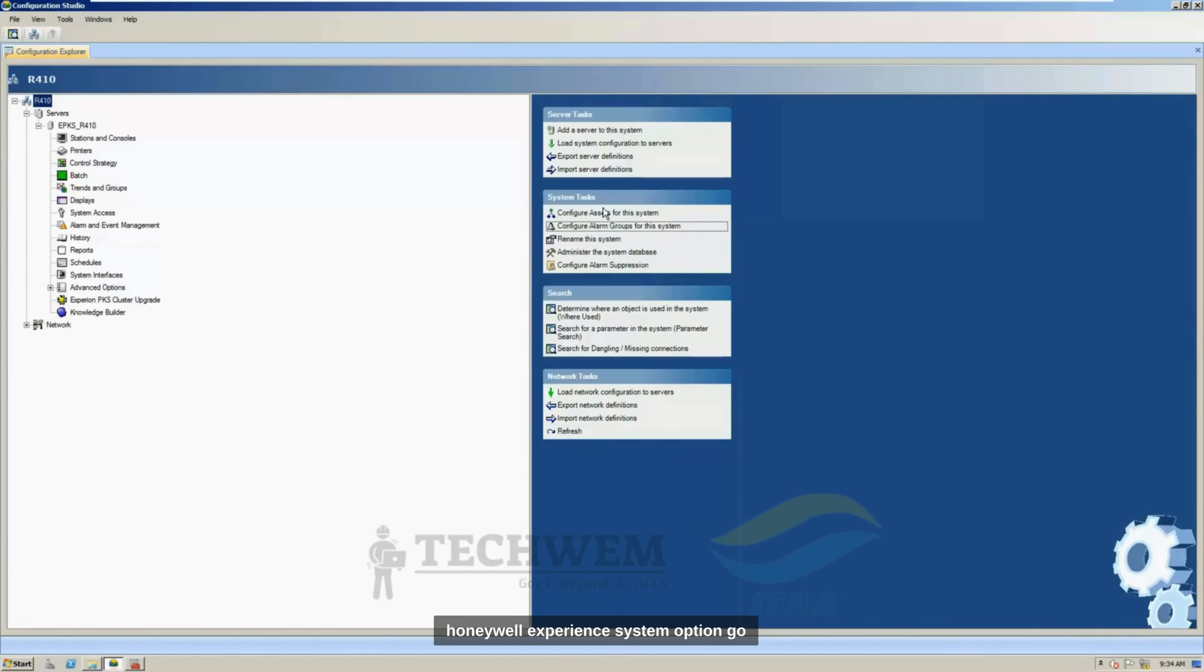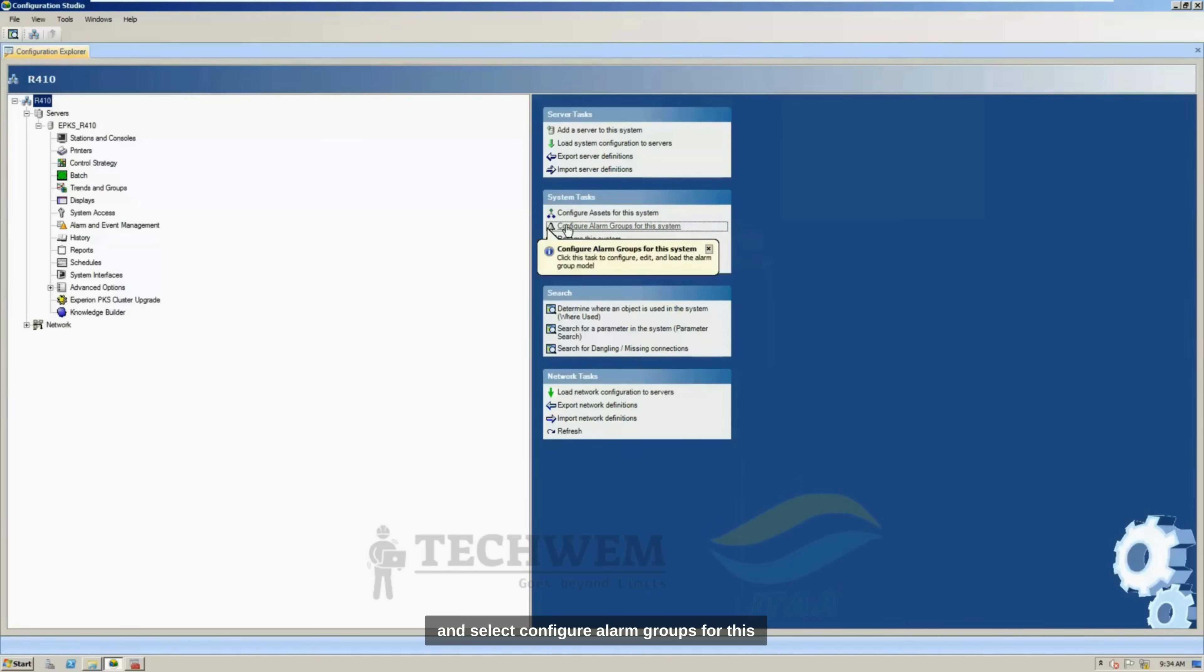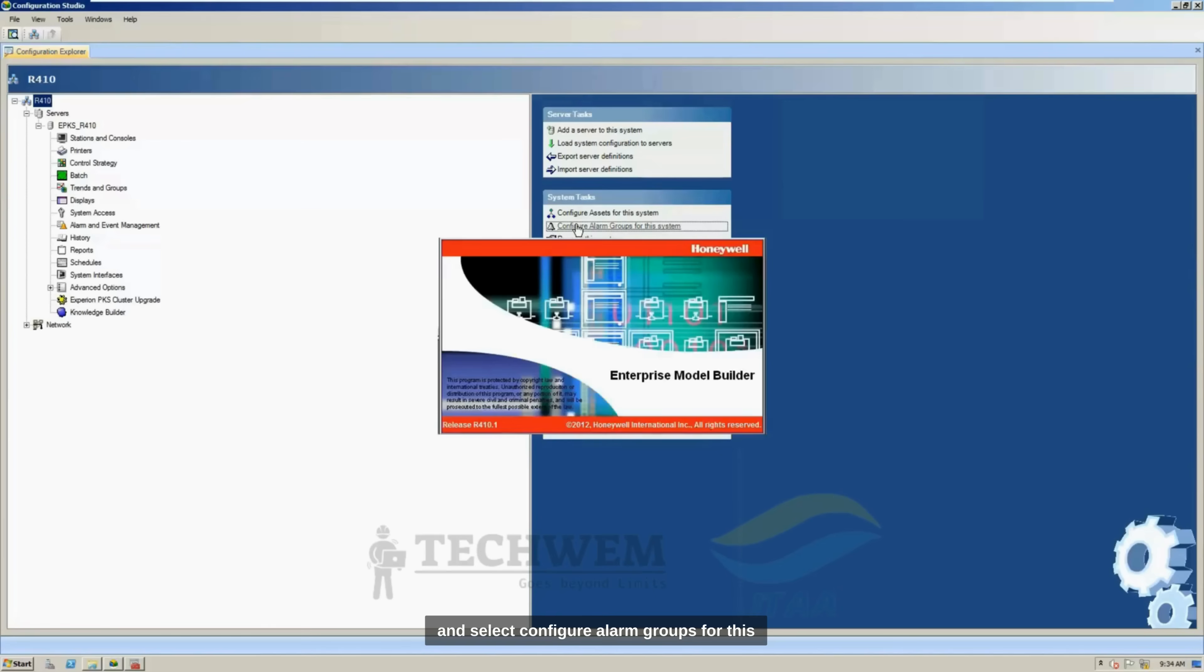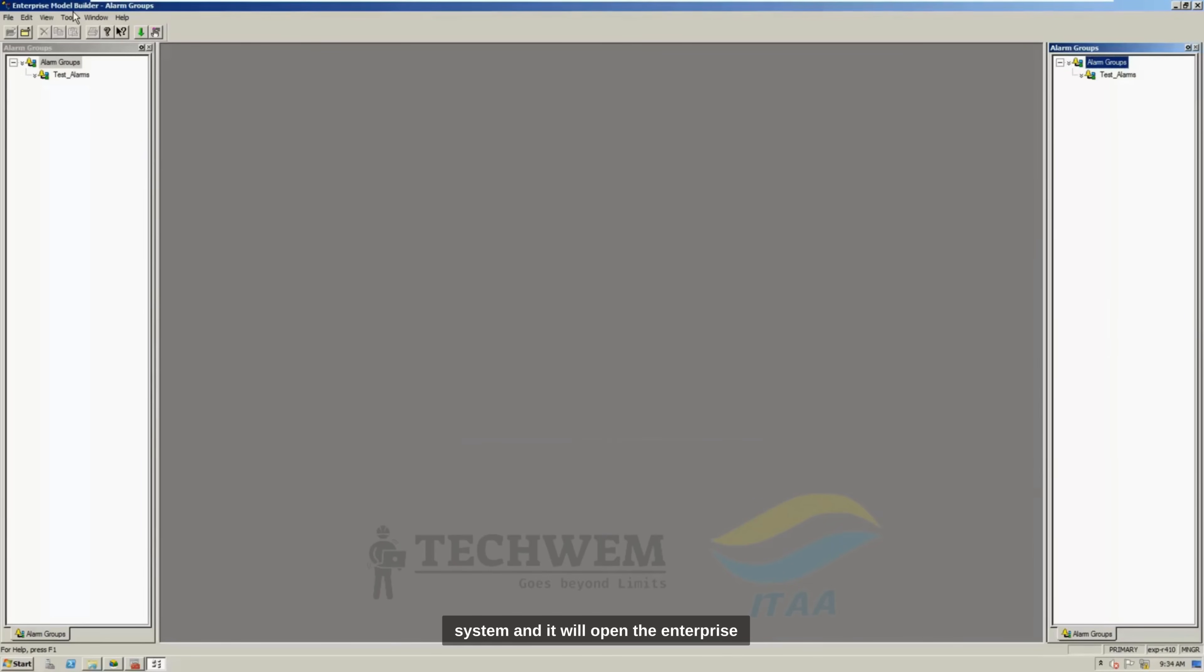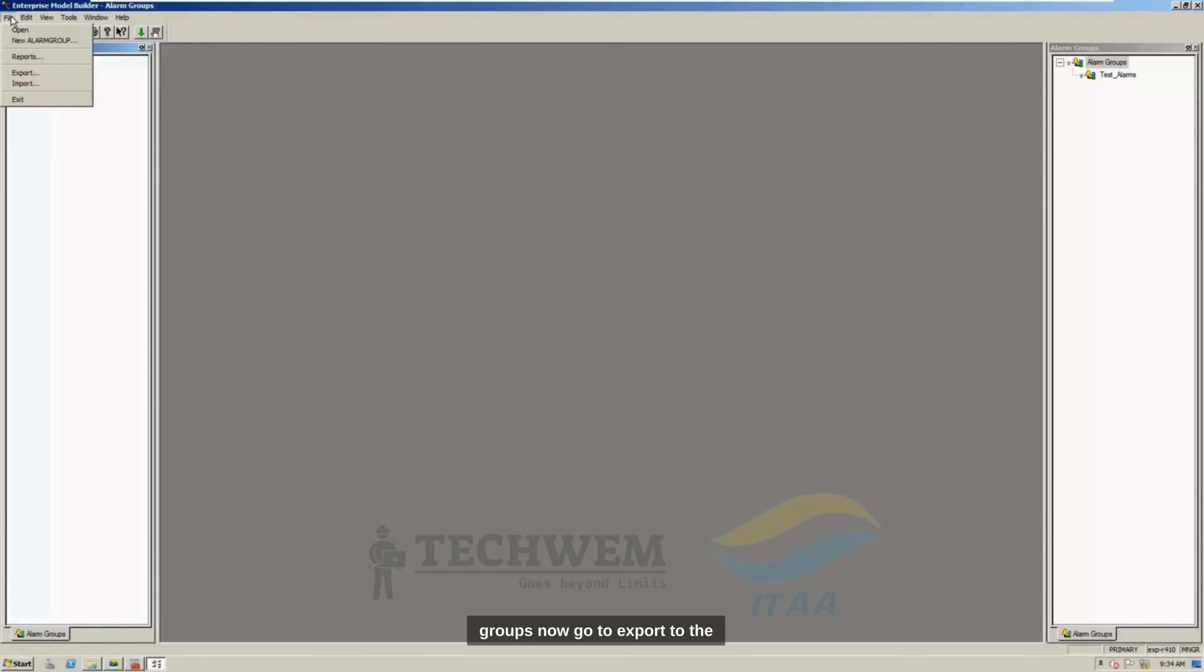Now, to take the Alarm Group backups, you need to go to Configuration Studio, select the system, Honeywell Experience System option, go on the right side to the system task, and select Configure Alarm Groups for this system, and it will open the Enterprise Model Builder Alarm Groups, and you can select all those alarms while hitting the Control button on the keyboard, and clicking on each of these alarm groups.